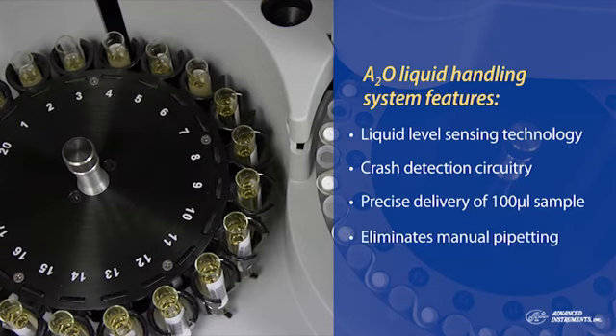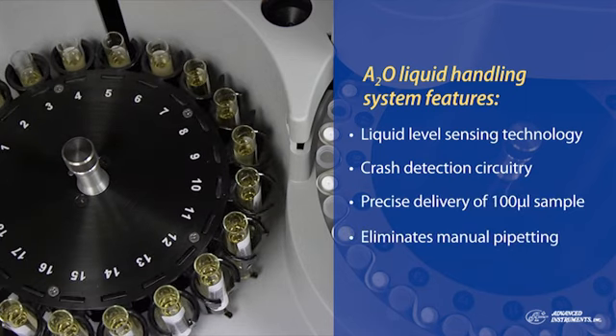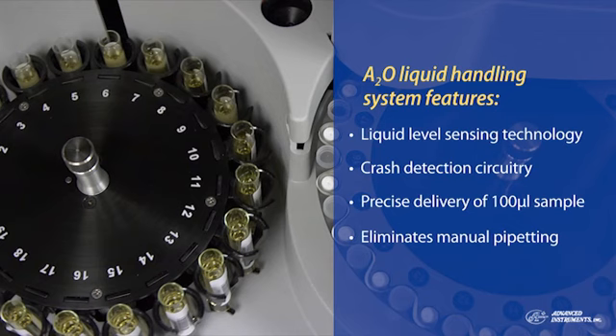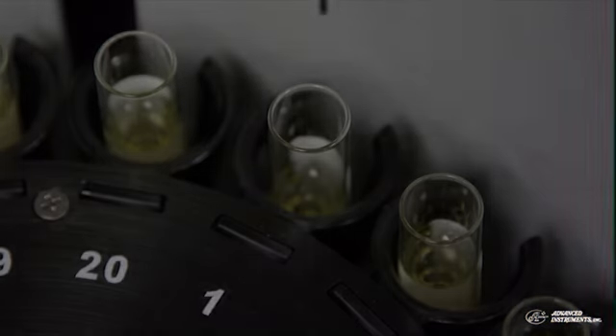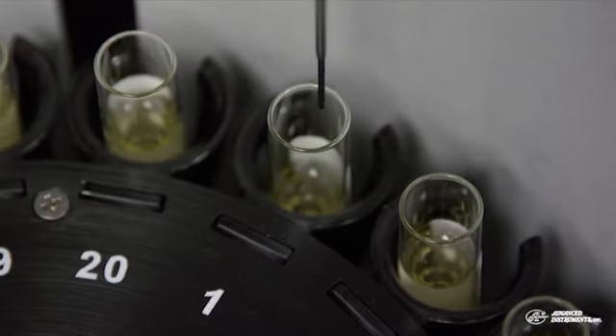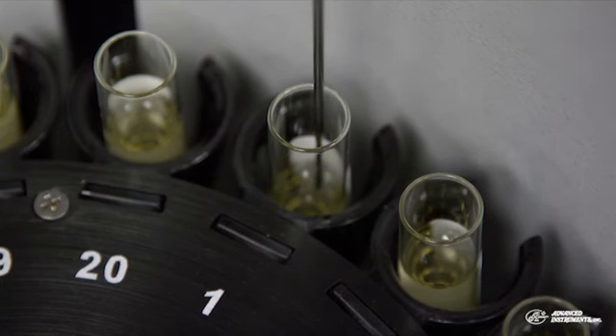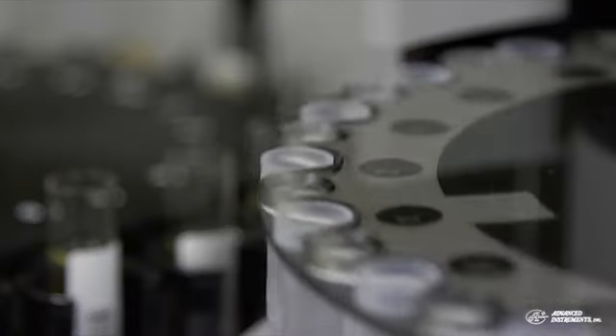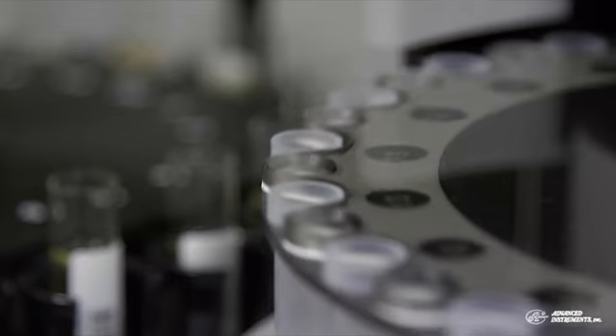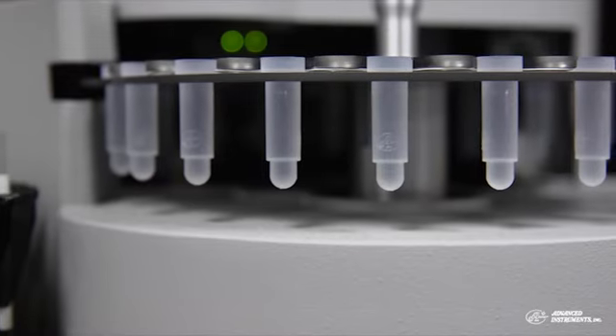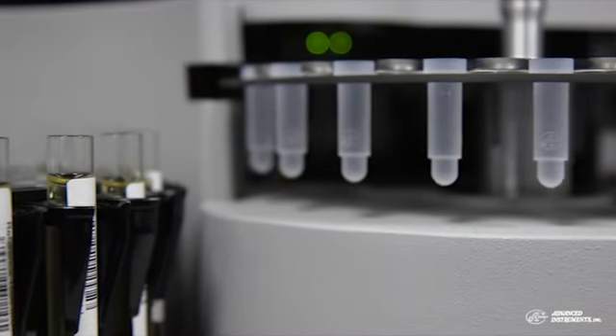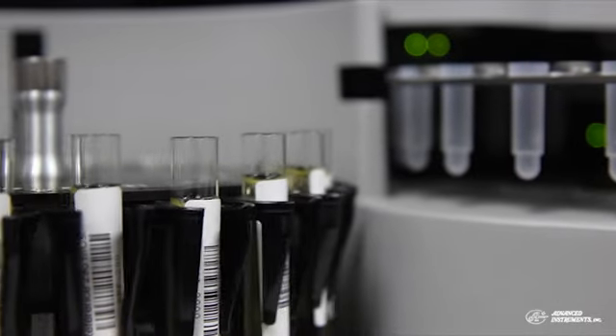At the heart of the A2O is an intelligent liquid handling system featuring both liquid level sensing and crash detection capabilities. The pipette system automatically detects the level of the sample in the tube and precisely transfers a 100 microliter sample to a clean sample cup in the osmometer carousel. This eliminates any manual pipetting, which often results in sampling errors and inaccurate test results.